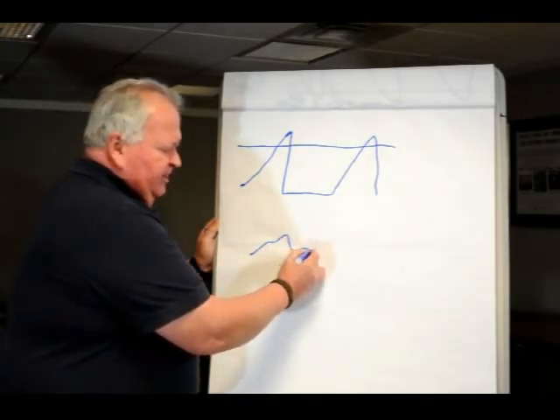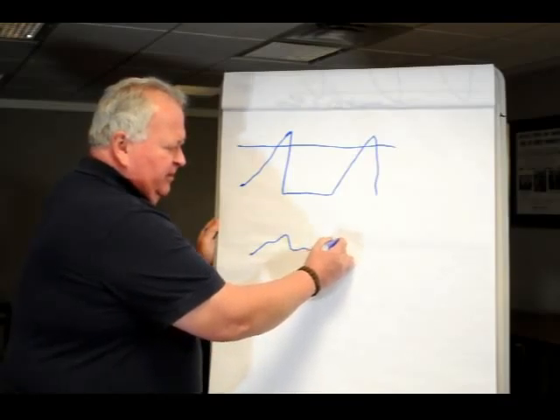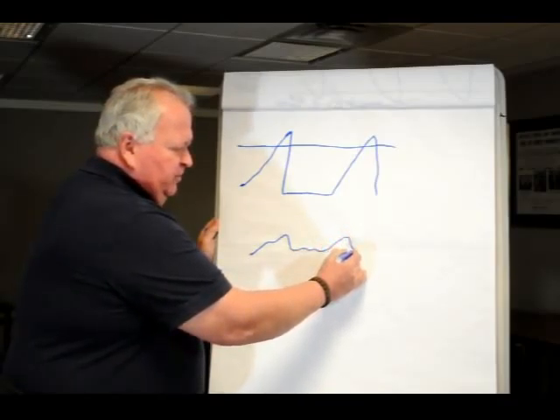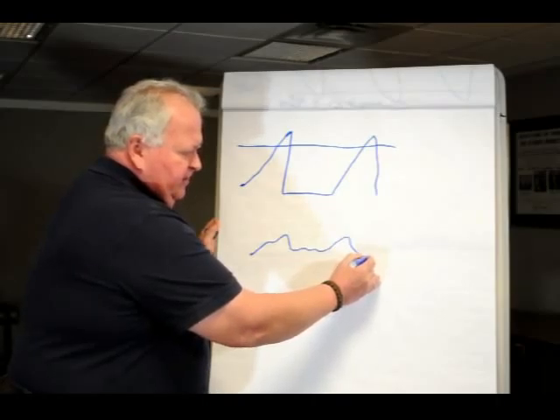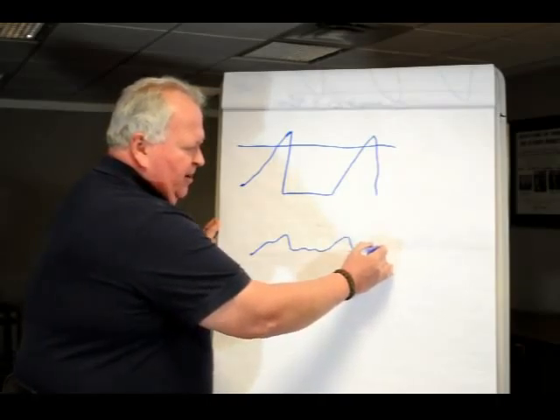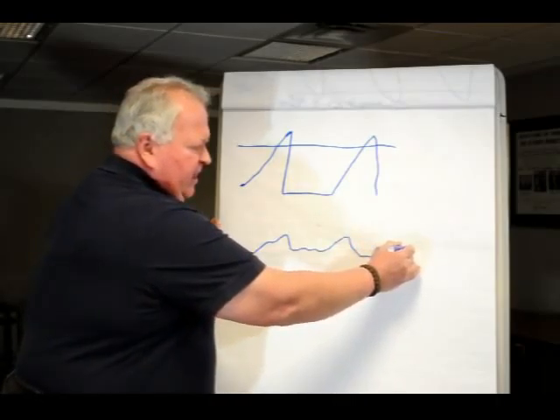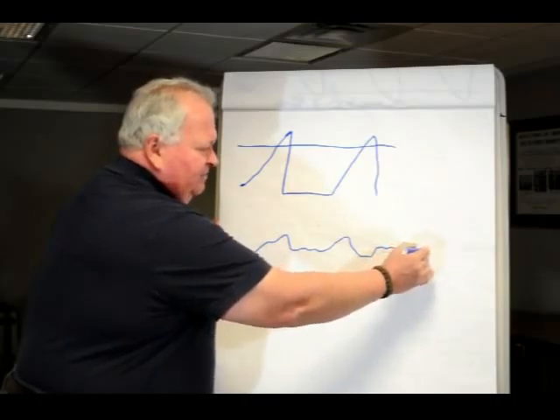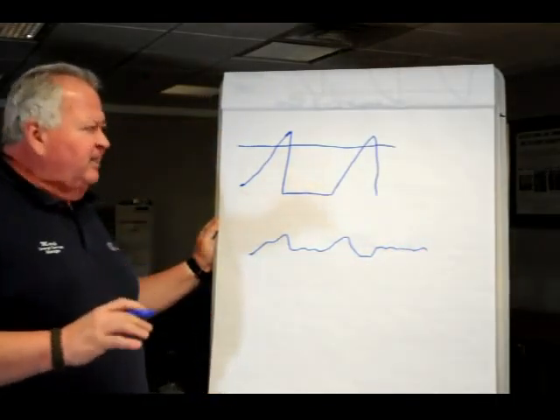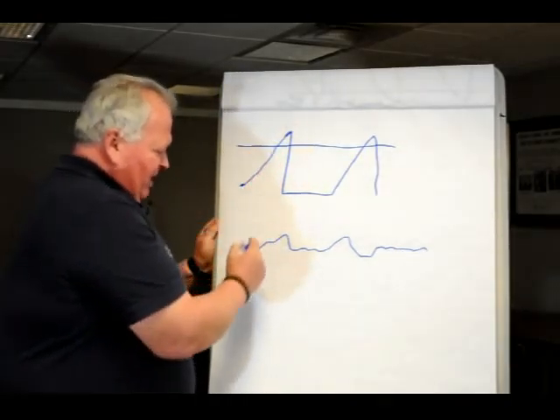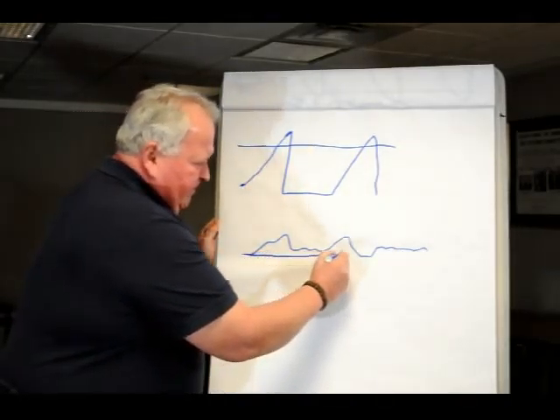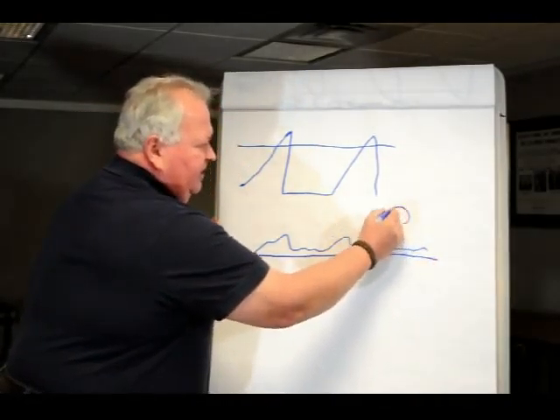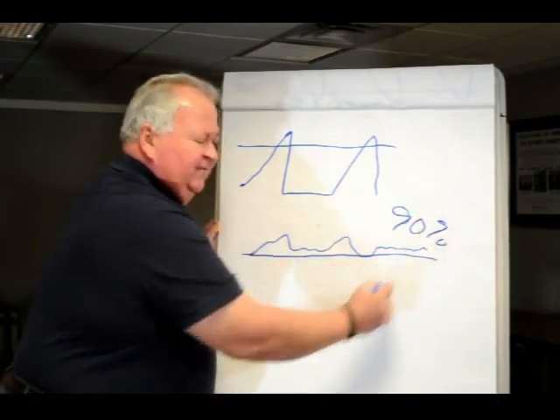And we're going to try and continue to maintain a temperature. If we do achieve temperature, we will indeed shut off for a period of time and then come back on and maintain. And when we can maintain a temperature, we're in that steady state efficiency roughly 90% of the time.